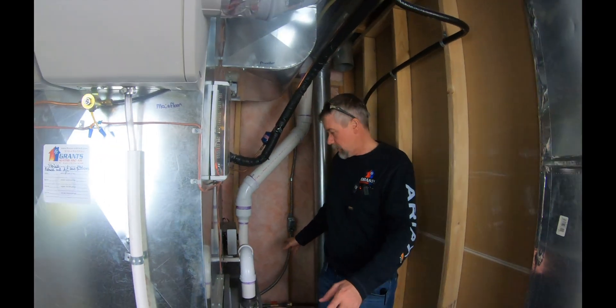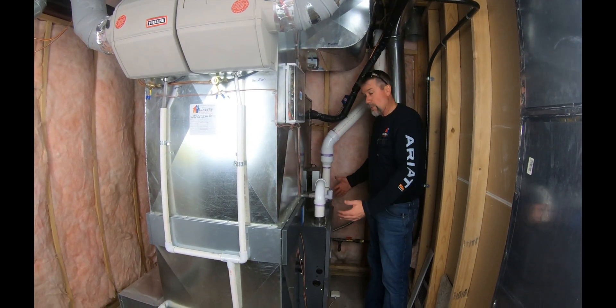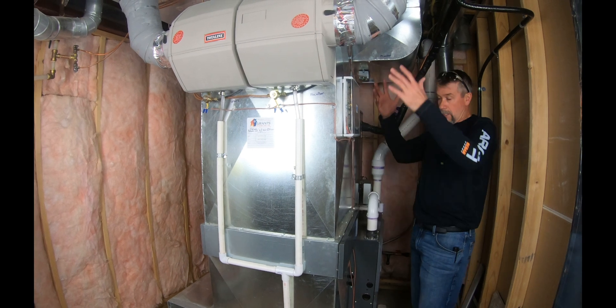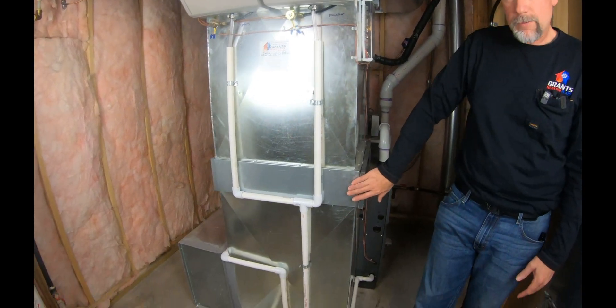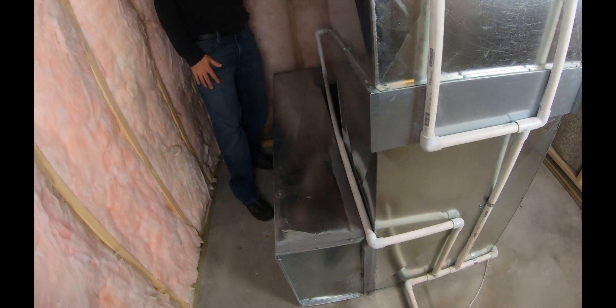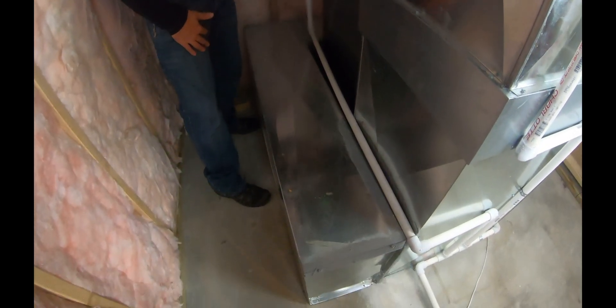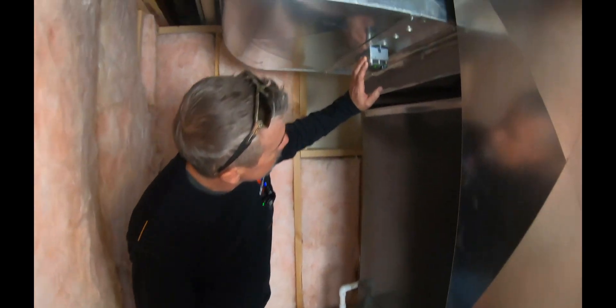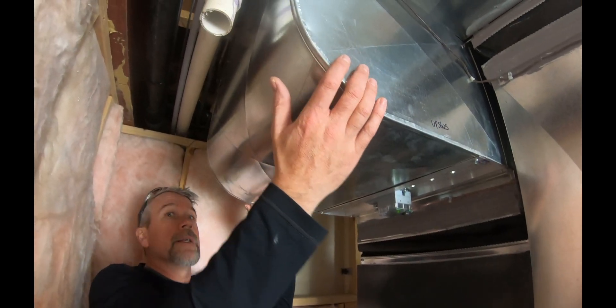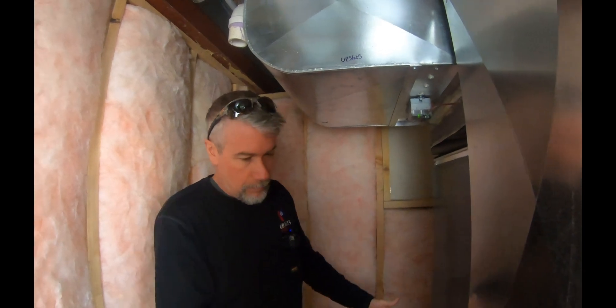On this five-ton furnace we needed to pull return air from the side, the bottom, or both sides — and that's what we've done. We made a return drop as big as the 20x25 filter, bringing all that air down and filtering it with a high-efficiency filter. We brought the ductwork around the back side to pull return from both the right and left sides of the furnace using a transfer piece of duct. Back here you can also see the other zone damper — these are really nice units with an indicator light showing what they're doing.